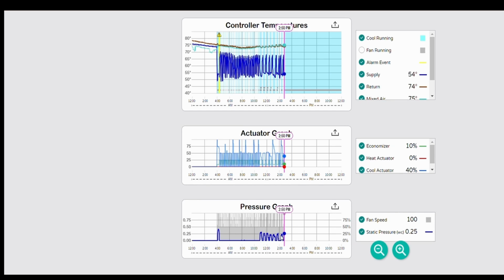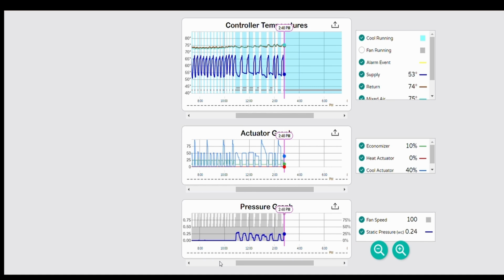So the pressure's really low, and it only seems to get up there when you have a longer call. If we zoom in, you can see how these little short calls do nothing - they don't register on the sensor at all. But if it's allowed to run for a while, it seems to build the static pressure enough to affect the sensor. So the sensor's probably in a bad spot - that's really probably what it is.